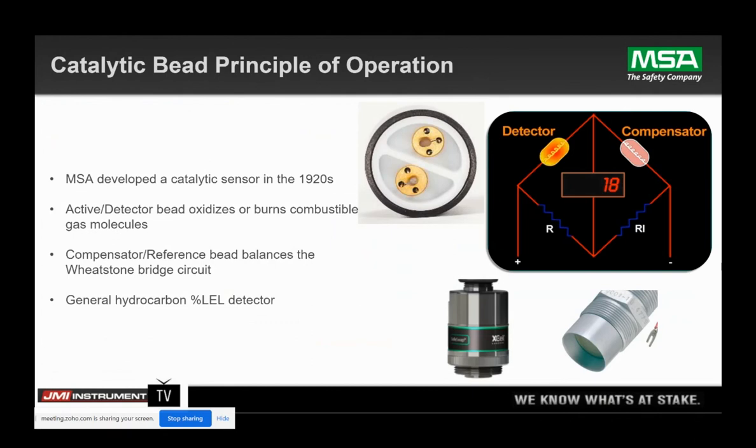In a nutshell, this is what a catalytic bead sensor is. As mentioned, it was developed in the 1920s. What you see here is really a Wheatstone bridge. You have an active sensor, and then you have a compensator or reference sensor on the other side of the Wheatstone bridge. The gas that comes in contact oxidizes or burns on the active side and creates a resistance on that Wheatstone bridge that's proportional to your LEL.